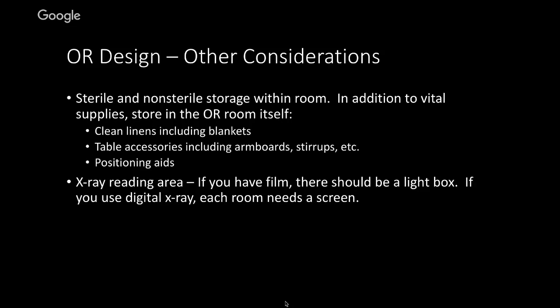Again, as we mentioned, in the operating room, there's going to have to be both sterile and non-sterile. I like to put the cupboards literally through the wall so that the people in the central core can open up the glass doors on one side, put the equipment in, and then the people in the operating room can open the doors on their side and get the equipment out. That keeps them from going in and out of the operating room and getting turbulent airflow that you don't want as well. And it's more convenient.